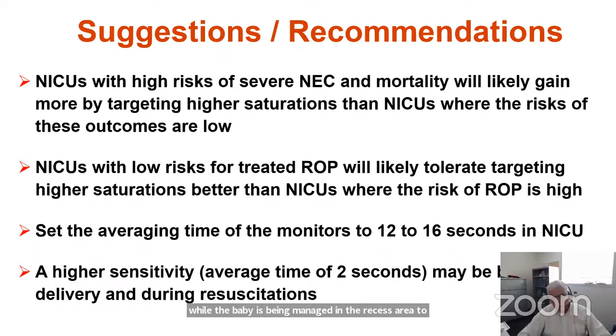ICUs with a high risk of severe NEC and mortality will likely gain more by targeting higher saturations than ICUs where the risk of these outcomes is low. ICUs with a low risk for treated ROP will likely tolerate targeting higher saturations better than ICUs where the risk of ROP is high. Set the averaging time of the monitor to 12 to 16 seconds when the baby is in the ICU, but that averaging time should be reduced to 2 seconds while the baby is being managed in the resus area to have a higher sensitivity for desaturation.